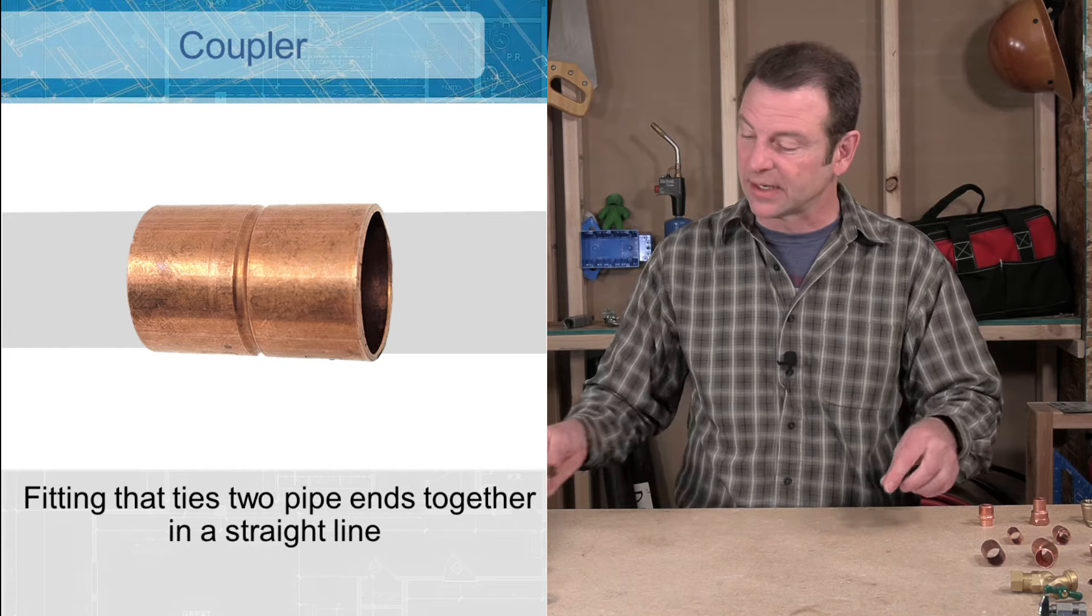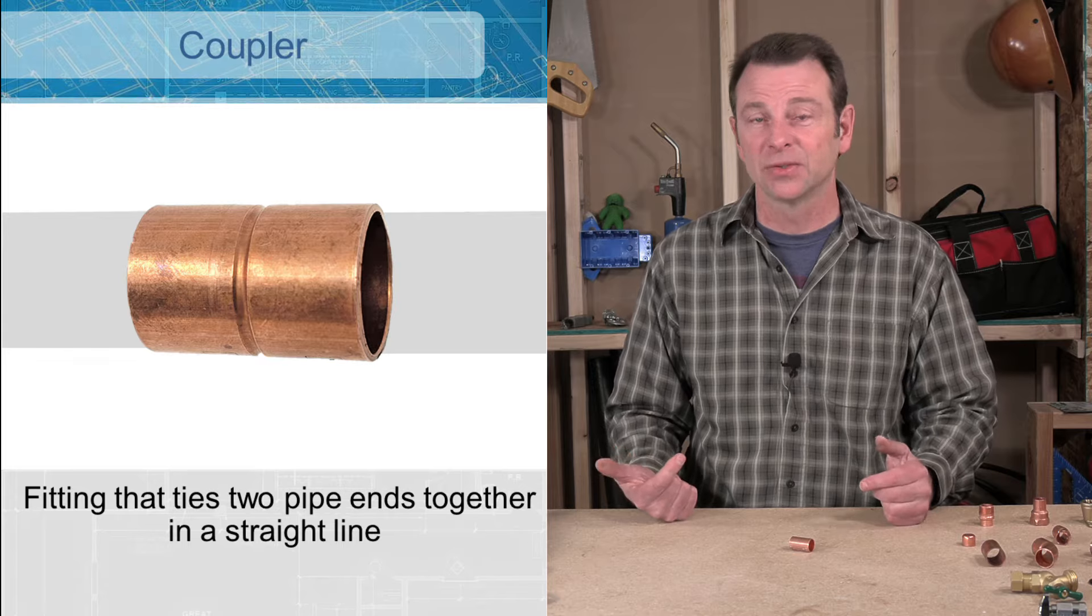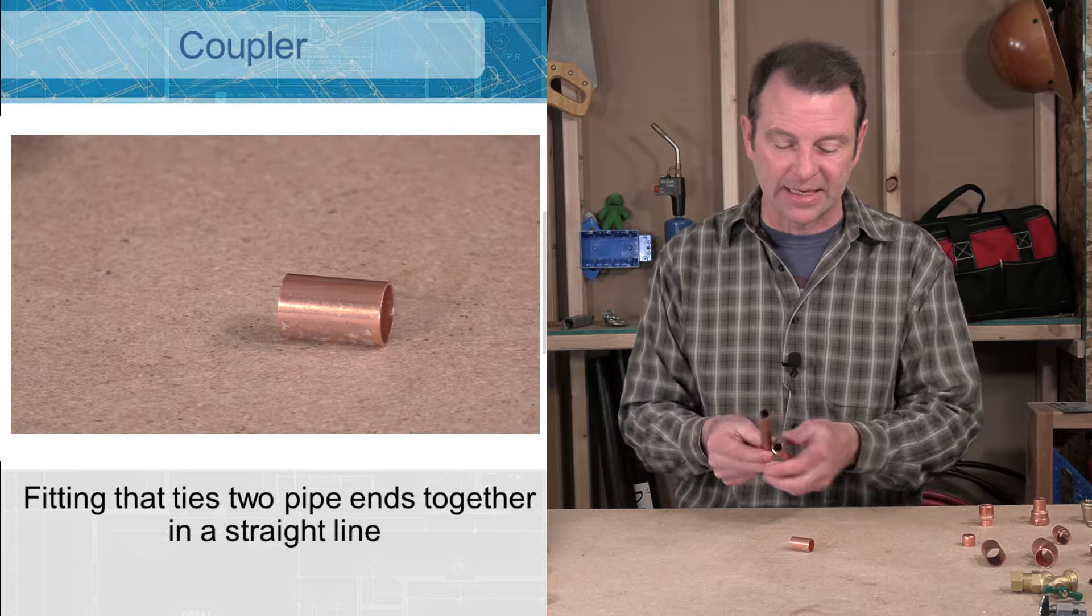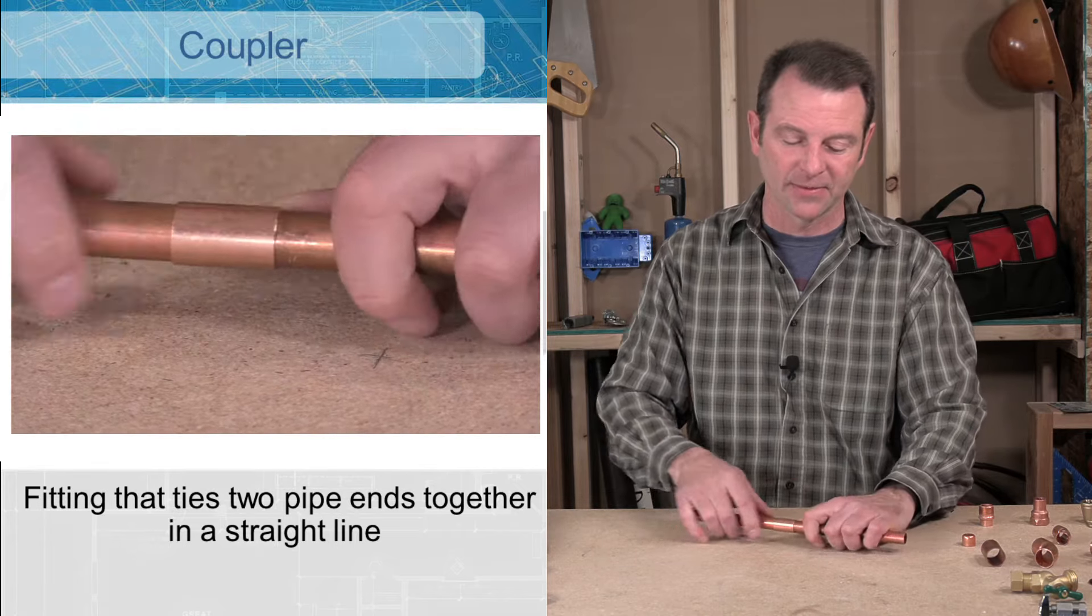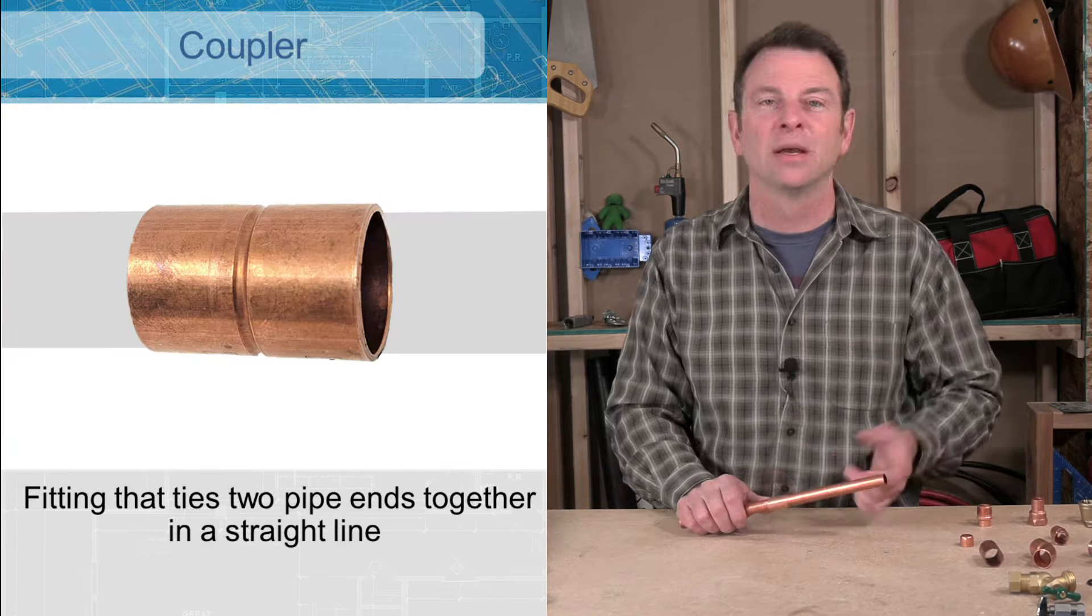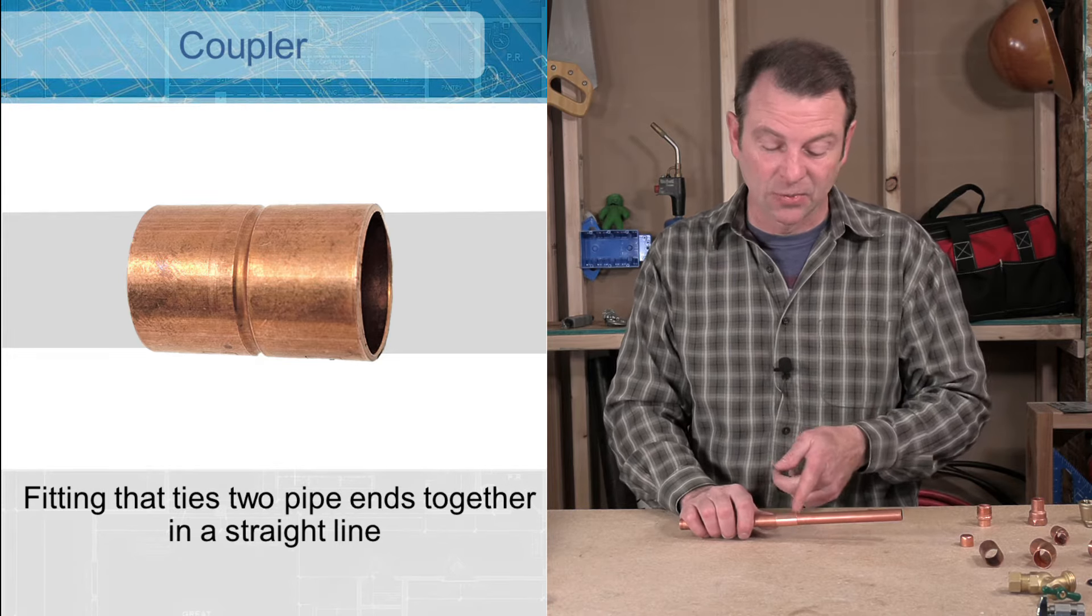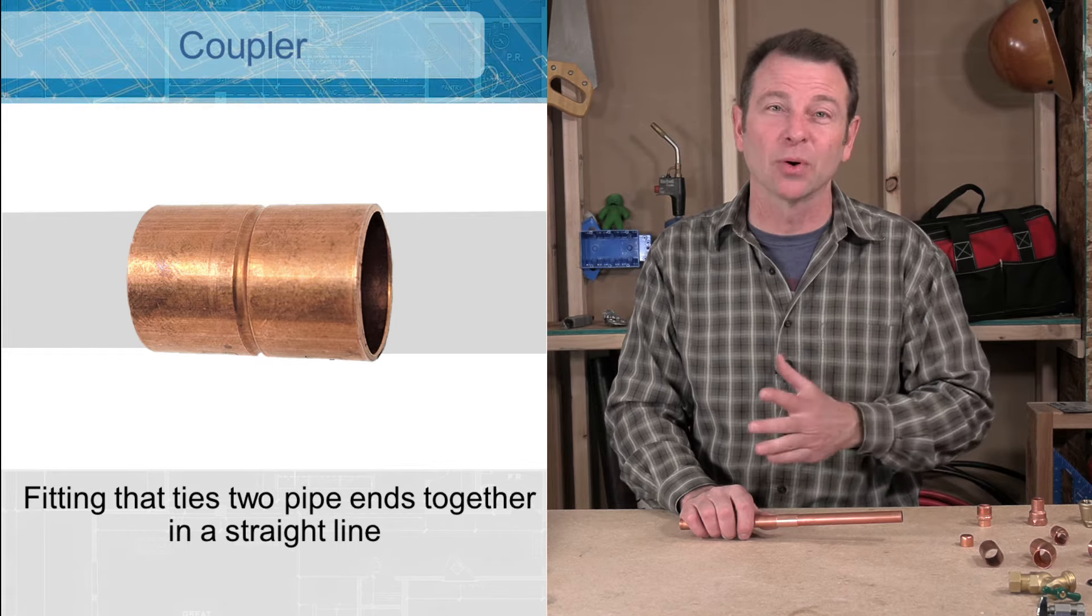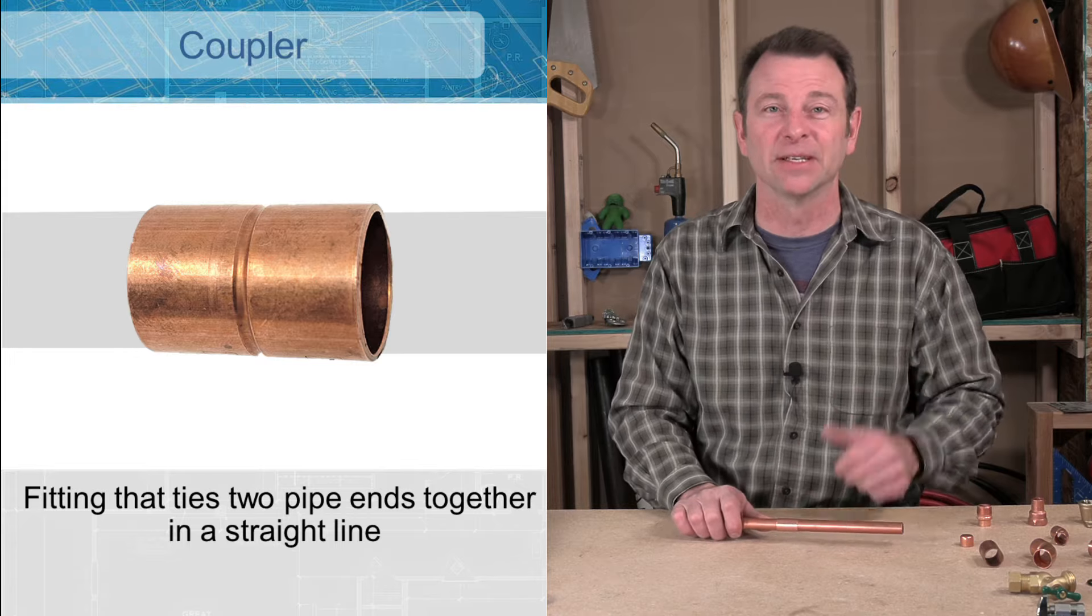The next one is a coupler. A coupler would be a fitting we would use to connect two straight pipes in a straight run. So I have a pipe that comes in from one side slips in here and then a pipe that comes in from this side slips in here and it makes a connection between the two. You can't see this, but there's a small notch on the inside of this fitting that will stop the pipes at the appropriate place. It's really important we get that full connection between everything. So make sure that you bottom out your pipes and your fittings.